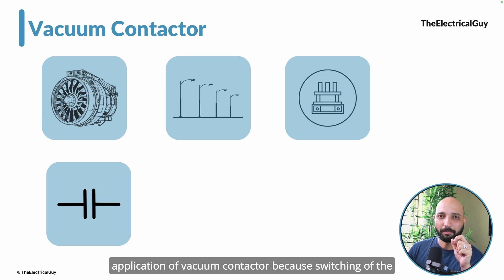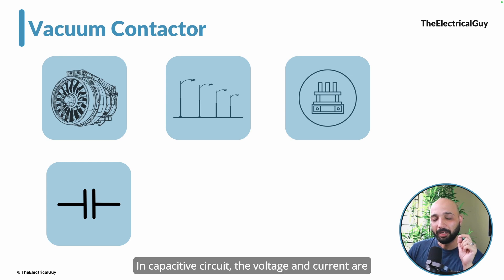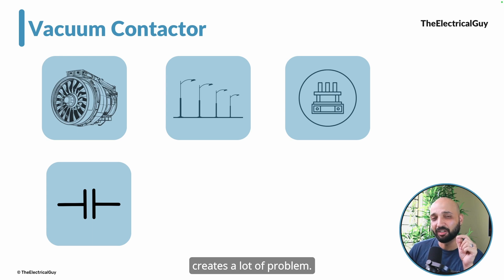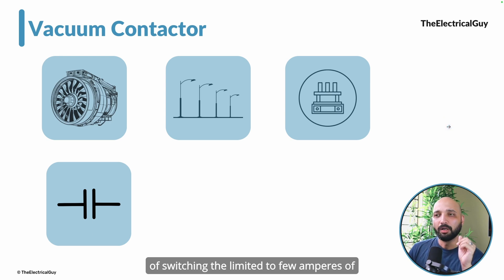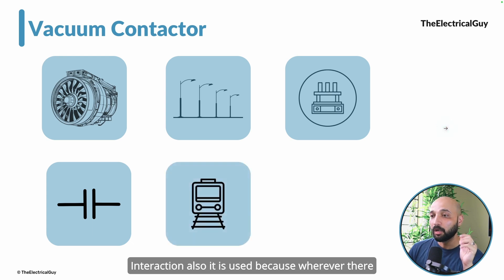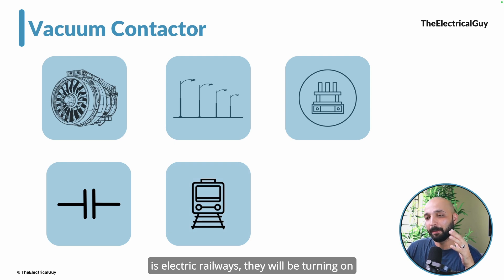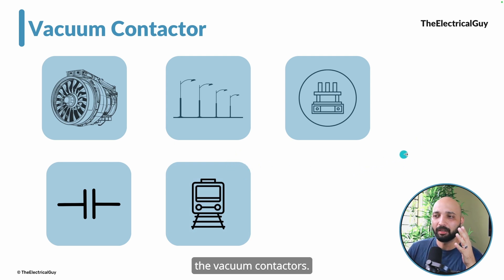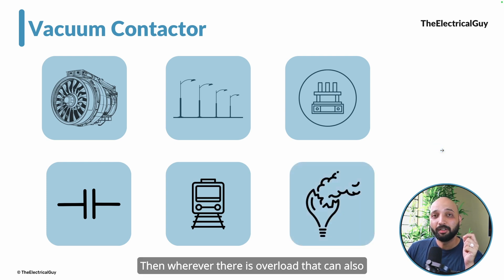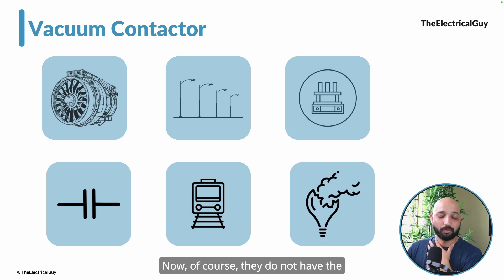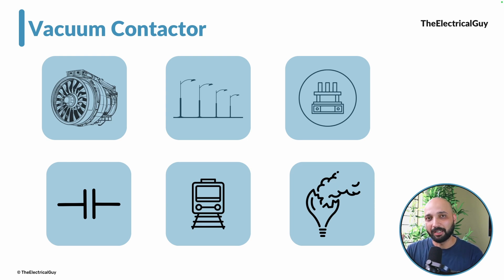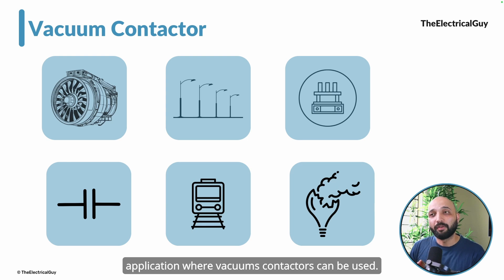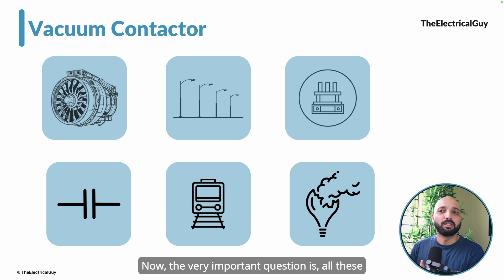Capacitor bank switching is another important application. In a capacitive circuit, voltage and current are out of phase by 90 degrees, which creates switching challenges, but vacuum contactors are capable of switching limited capacitive currents. They are also used in electric railways for turning supply on and off. Additionally, where overload conditions occur, vacuum contactors can support that, and when coupled with a fuse in series, they can also provide overload and short circuit protection.